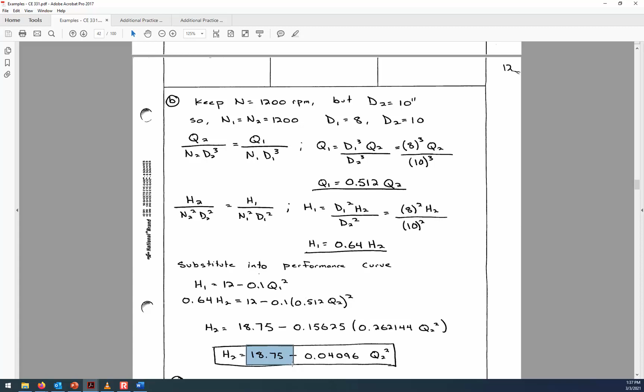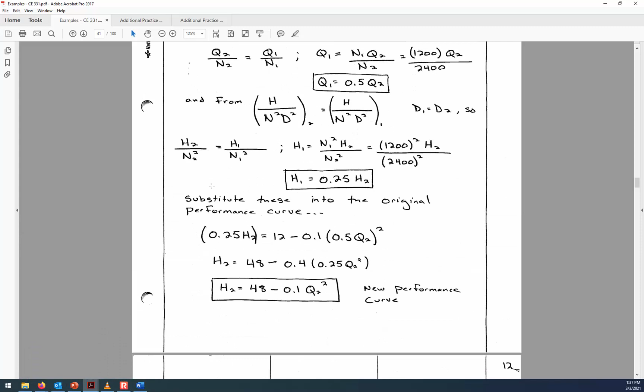So this original pump performance curve doesn't work. In question A, where it was 2400 RPM, remember the cutoff head was 48 feet, so that will work. The second situation you just worked has a cutoff head below 30 feet, so that won't. So to lift the water 30 feet, you'd need to go with the 2400 RPM rotational speed and the original 8-inch diameter impeller. We could also change both things simultaneously - for example, switching to a 10-inch impeller rotated at 2400 RPM. These scaling laws let us adjust multiple parameters at once.